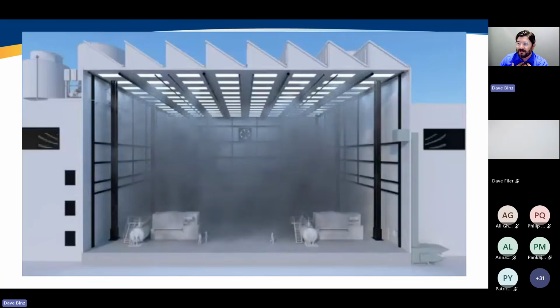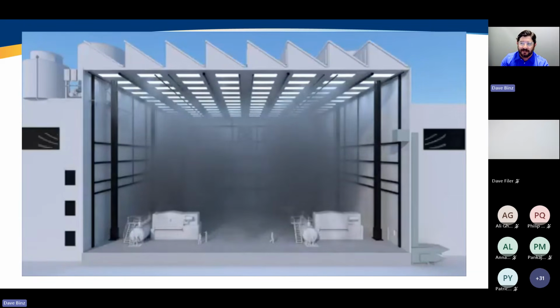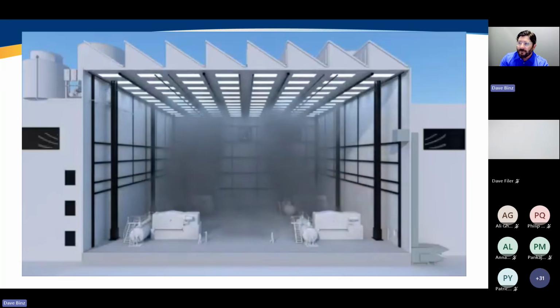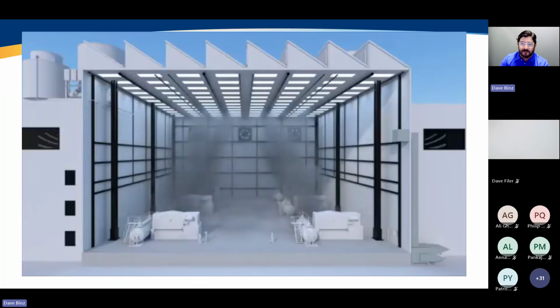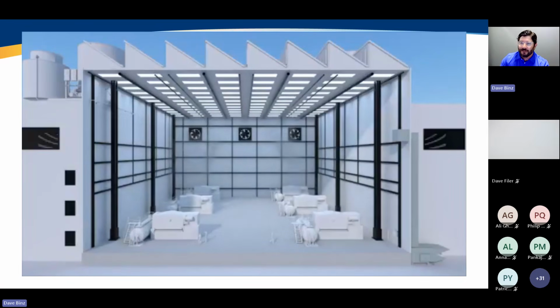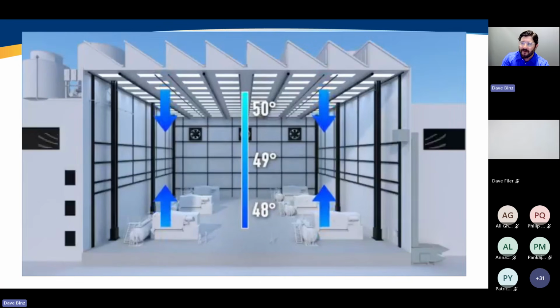And oftentimes HVAC experts and engineers don't come in until after an indoor air quality problem has already existed. So you've got a building, they added process, they added indoor contaminants. What's the first thing we do? Well, we've got to solve the indoor air quality problem. Let's add some exhaust fans. So they add exhaust fans, capturing and containing all that exhaust. However, they didn't look at how it's going to impact the indoor environment from a temperature perspective. So a building that was cool and comfortable at 65 degrees, now I've added a lot of exhaust. It's a negative building, negative pressure. I've got all this untreated, untempered infiltration coming in, and our temperatures are dropping. And so that's often when we get involved on the solutions.